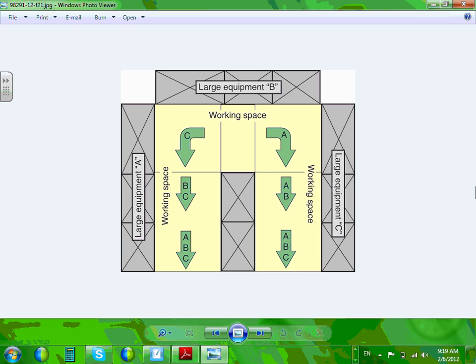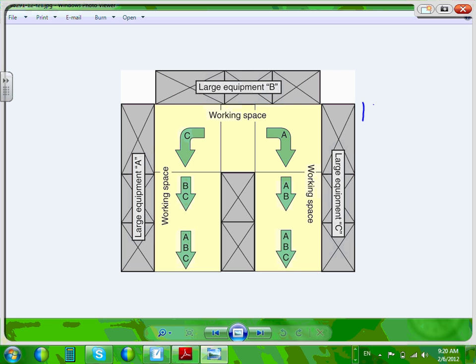Large equipment, guys, is how they define it: 1200 amps and over 6 feet. I believe this is how they define it. If you have any piece of equipment that's 1200 amps and, I emphasize the word and, because people always ask whether it's or or and, this is and more than 6 feet, then you apply the large equipment rule.